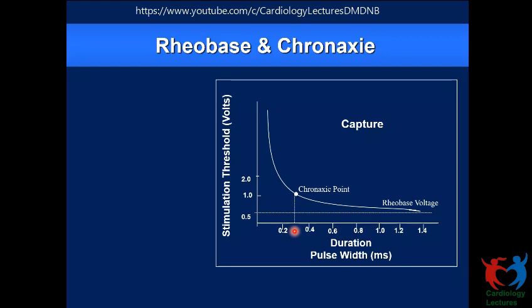We can similarly calculate different voltage thresholds for different pulse widths. Similarly, keeping the amplitude constant, we can determine the pulse width threshold for different voltage amplitudes. It is common sense to imagine that when the amplitude is higher in terms of voltage, the pulse width threshold is expected to be lower. There is a limit to that. Similarly, you can increase the pulse width and the voltage threshold will gradually come down to that minimum point, which is the rheobase voltage. No matter how much you increase the pulse width beyond 2 milliseconds in this case, it would not go any further. So each combination of amplitude and pulse width on the curve is a threshold point.